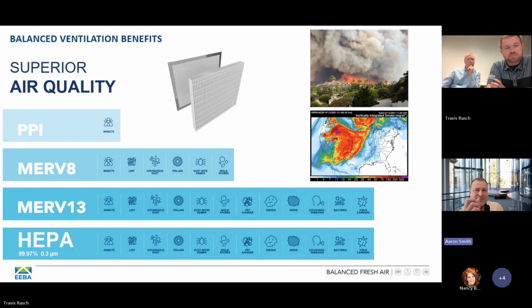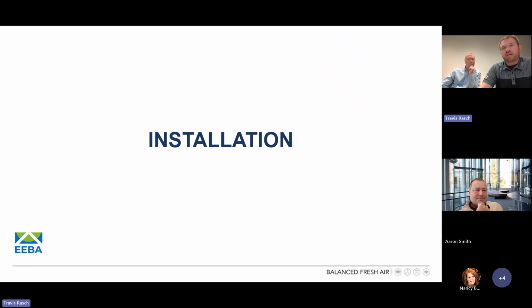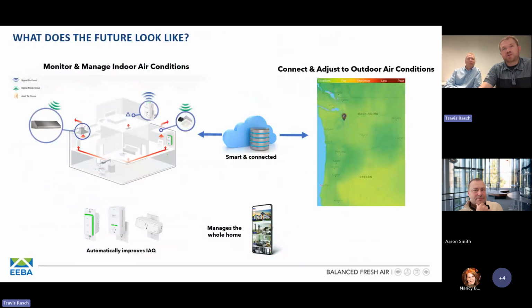But can you just talk a little bit about, I think you guys are really thinking critically about most of the time, 95% of the time, outdoor air is far better than indoors, but there is 5% of the time where outdoors is worse. Yeah, that's exactly why that integration to a number of weather stations, outdoor APIs, et cetera, being able to utilize all that data. Because we can make a stroke with a broad brush saying outdoor air is bad, but there's hyper local events, and that's where that outdoor API, grabbing that data from a very local source, can make a better decision versus just a broad, hey, it's a bad outdoor air day for the state of Minnesota as an example. But the reality is it might be a very local event, and it might be local fires or whatever it might be going on. So that's where being able to grab all that data and then make a decision based on it is where having this type of Overture system interact with our outdoor air devices, you can make those decisions autonomously.